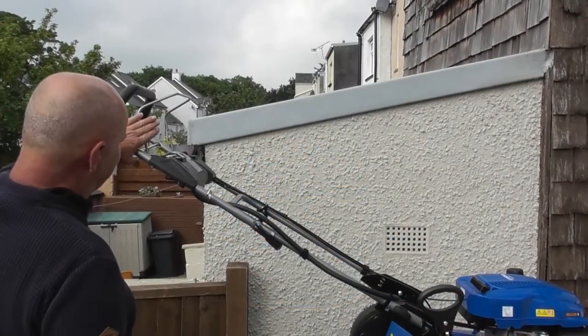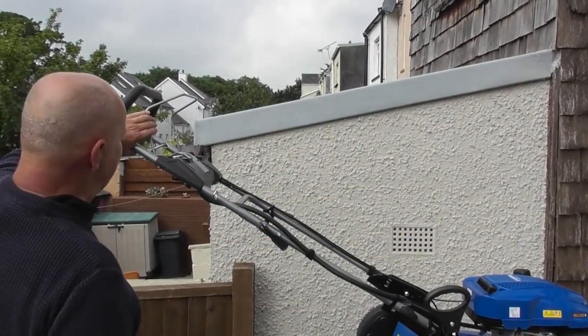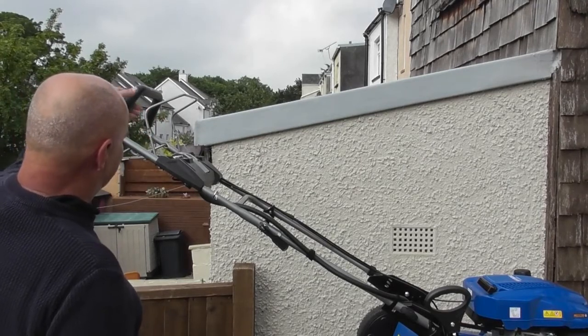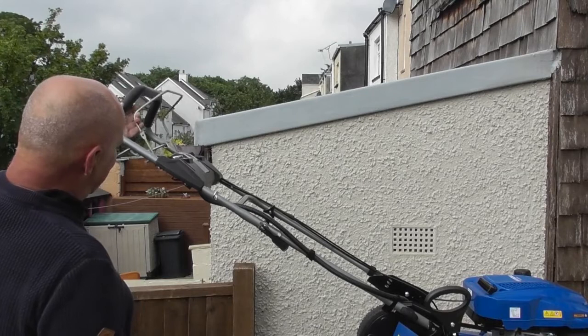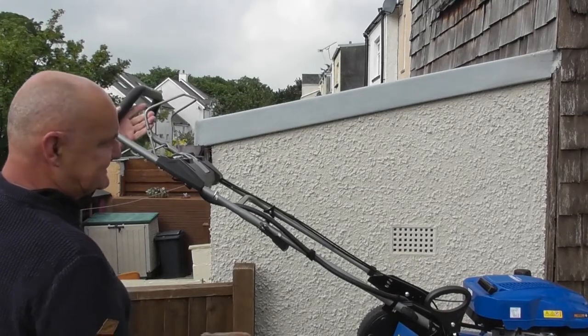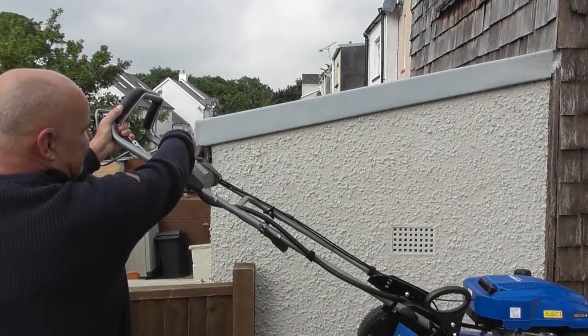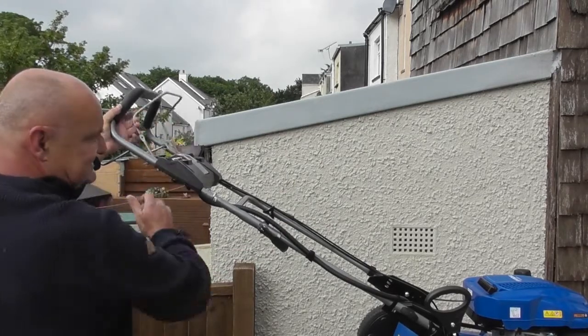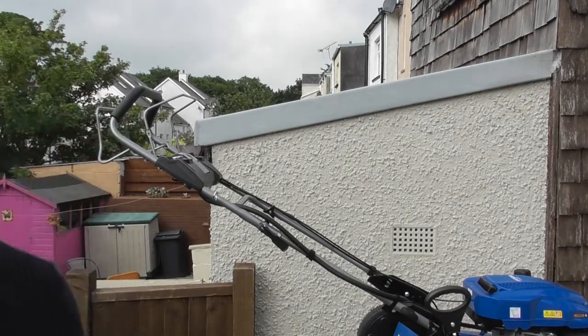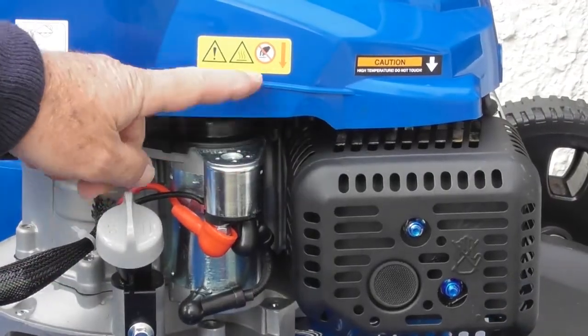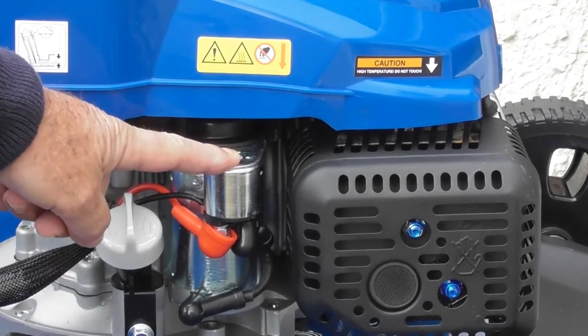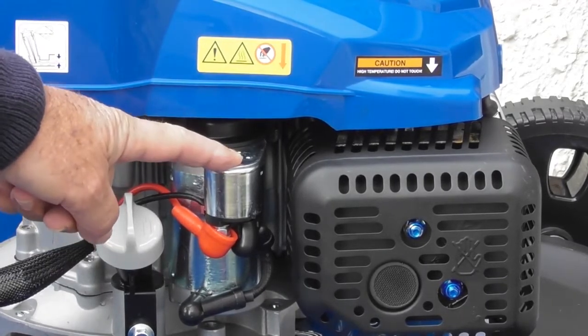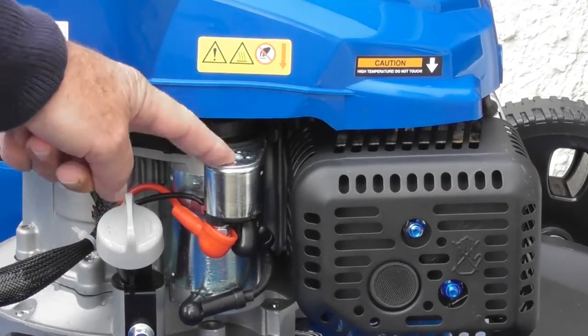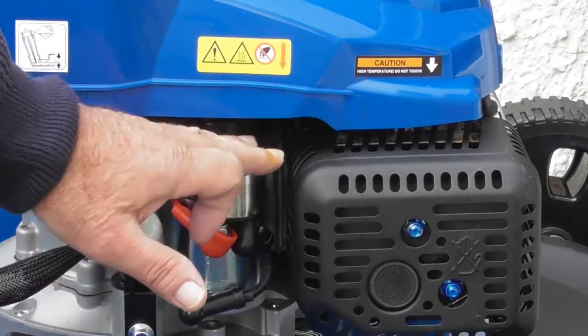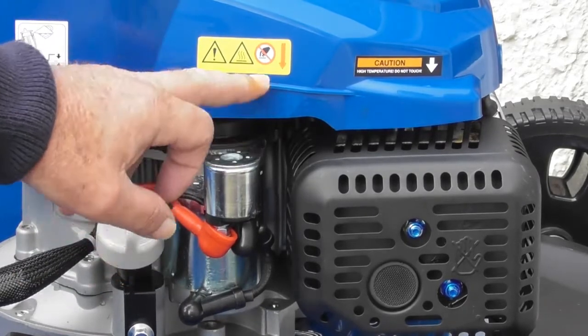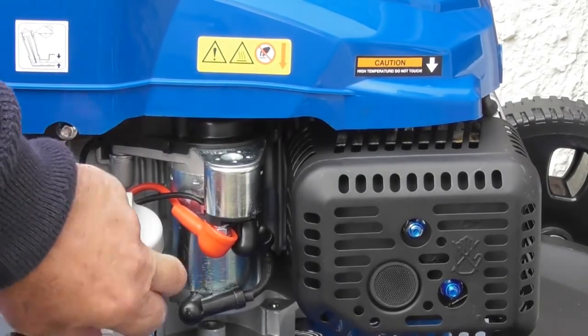As I mentioned earlier, we have 3 switches which all have to be made for the starter motor to engage. The first one is on the other end of the cable on the OPC, at the engine end. The second one is the start button itself - that's 2 switches. And the third one, we'll bring you across - it's actually a solenoid, but for our purposes we'll call it a switch. When the top 2 switches are pulled, this switch or solenoid should actuate, which engages the starter motor and starts the machine. So that's the third switch, and of course the starter motor is here.